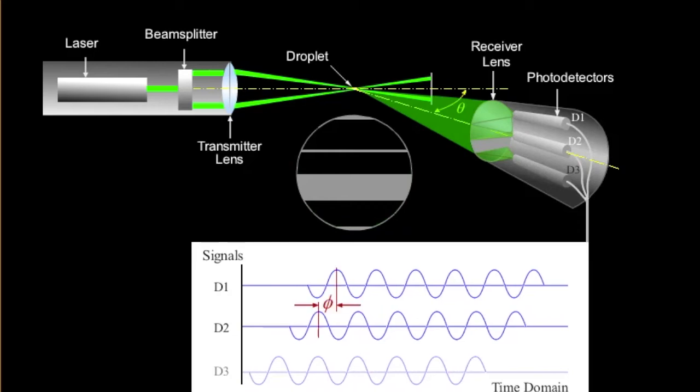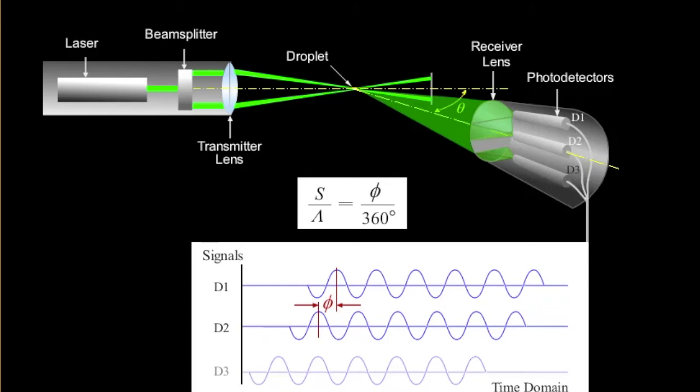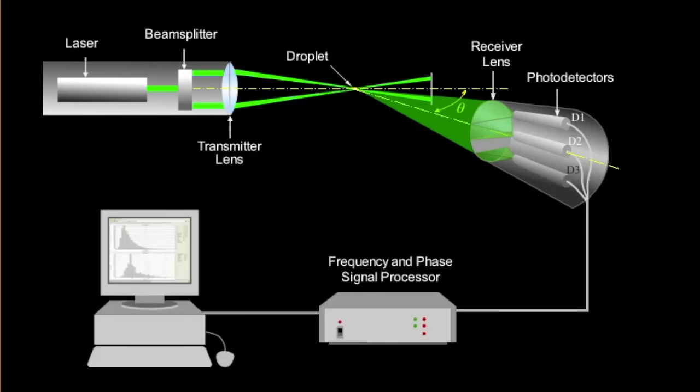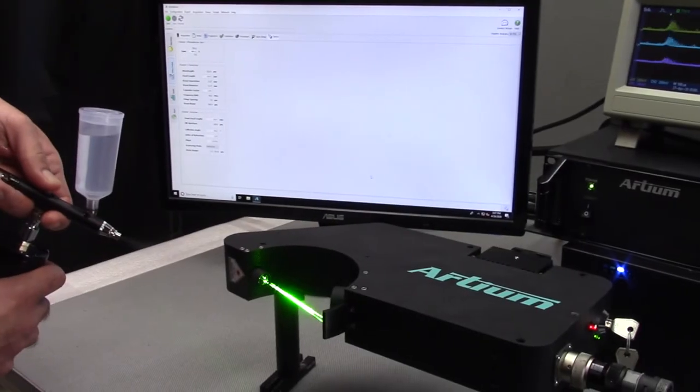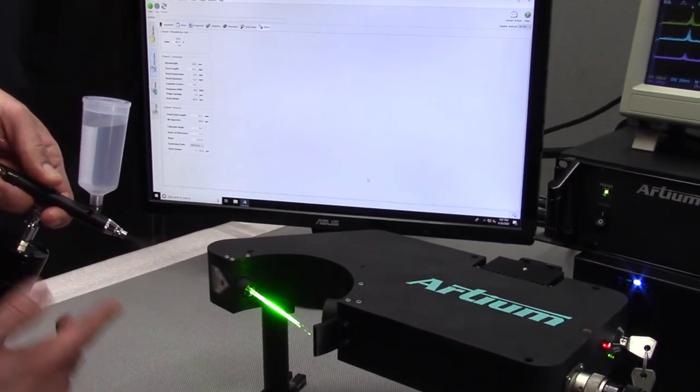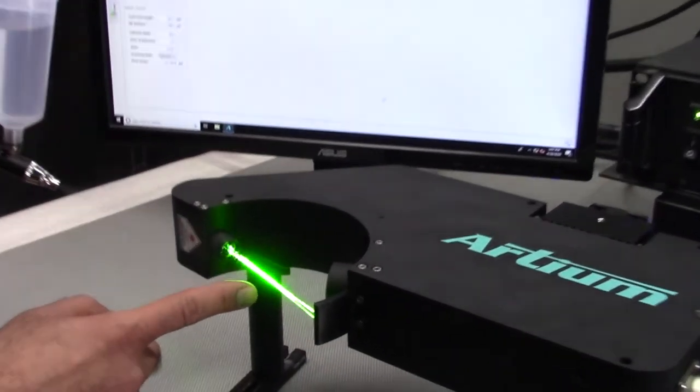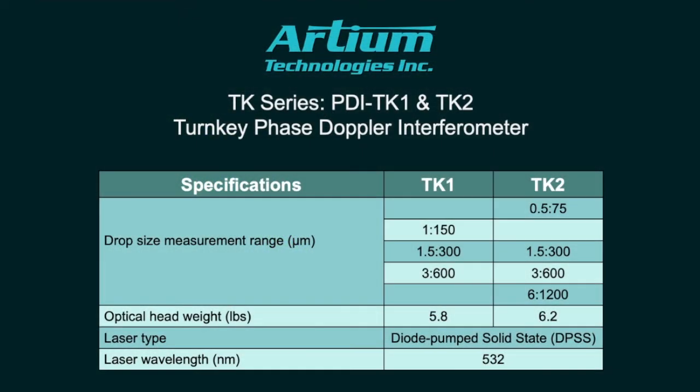Then we send those signals into the processor. And after some processing of the signals, we send those into the computer. And the software does the final calculation of the droplet diameter. The TK is one of many instruments Artium makes that uses PDI method. The TK itself comes in six or seven different packages and optical layouts to fit different applications. But we can also customize them to treat your application.